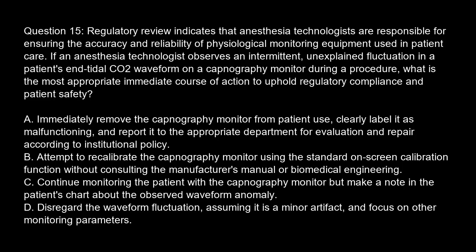Question 15. Regulatory review indicates that anesthesia technologists are responsible for ensuring the accuracy and reliability of physiological monitoring equipment used in patient care. If an anesthesia technologist observes an intermittent, unexplained fluctuation in a patient's end-tidal CO2 waveform on a capnography monitor during a procedure, what is the most appropriate immediate course of action to uphold regulatory compliance and patient safety? Option A. Immediately remove the capnography monitor from patient use, clearly label it as malfunctioning, and report it to the appropriate department for evaluation and repair according to institutional policy.